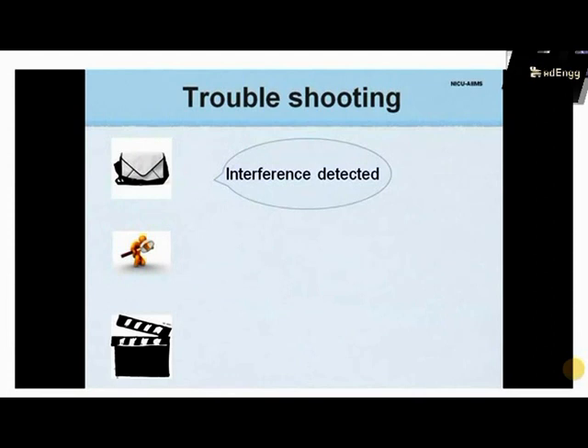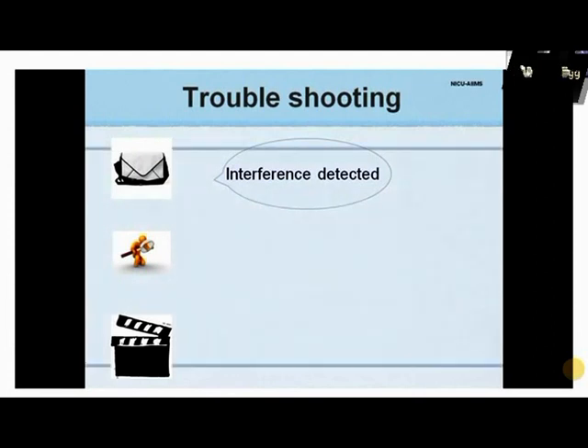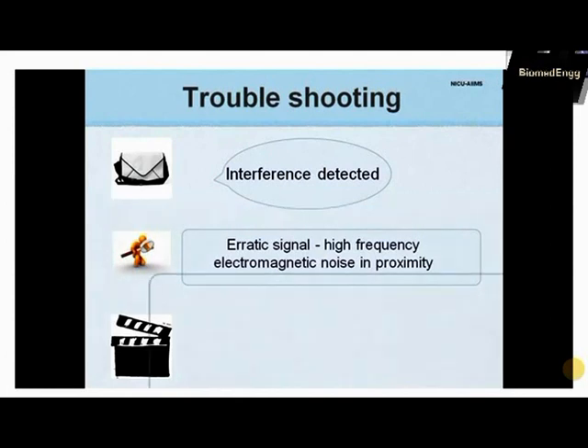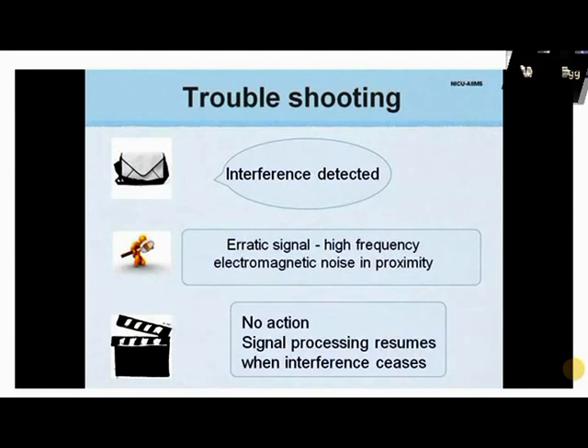If interference is detected, it means the signal is too erratic to be processed due to proximity of electrical equipment generating high-frequency electromagnetic waves. Generally no action is required, as readings either remain unaffected or display dashes if the interference persists. Signal processing resumes when the interference ceases.